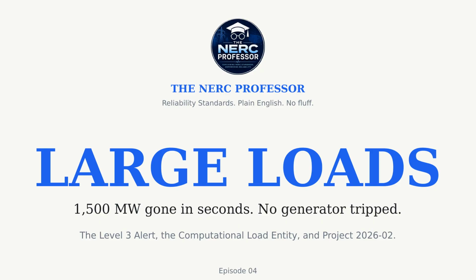A lightning arrestor fails on a 230 kilovolt transmission line. The protection system does exactly what it was designed to do. Every fault clears correctly, the slowest one in 66 milliseconds. And then 1500 megawatts of demand vanishes from the Eastern Interconnection in seconds. No generator tripped, no utility breaker dropped a single customer. The grid didn't disconnect that load; the load disconnected itself.